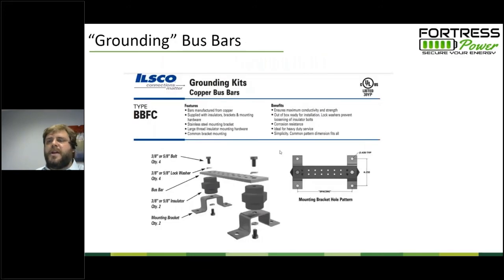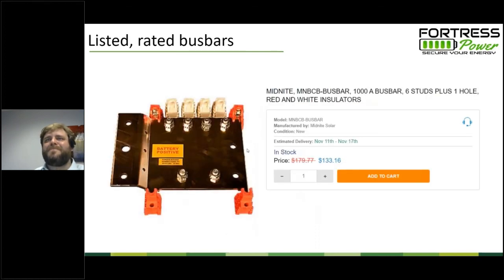The bus bar is not listed for use. If you pull open ILSCO's spec sheet on these things, the bus bars don't have amperage ratings. They don't have voltage ratings, because ILSCO has not been listing them for power distribution. So they're not going to give you that rating anyway. And so you may have to suck it up and recognize that the DC side components do cost money.